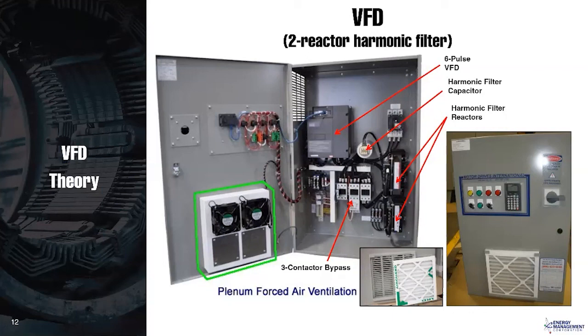And we put our filters right on the outside. That's a standard pleated furnace filter, and it's pretty easy to see if it's dirty. If you have filters behind louvers, we find they tend not to get changed. But in this case, that filter's right on the outside, and it does get changed. We believe in the religion of keep the drive clean, keep it cool, and keep it dry, and it will last a long, long time.